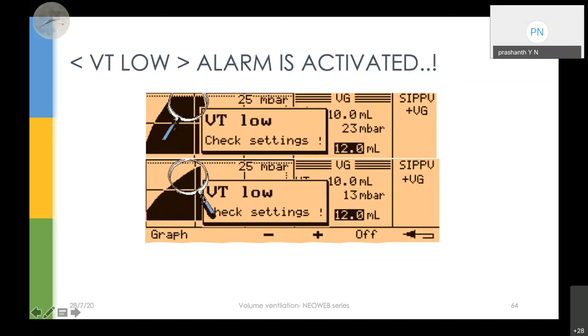And this is another example of VT low, where you see that there is no plateau in your pressure graph. Maybe you look at the flows, and they are also normal. Now you probably need to look at the I time, because if you have decreased your inspiratory time, your pressure graph is getting cut off before it delivers the tidal volume. Here in this case, you might have to increase your TI based on your flow graphs, the flow scalars.